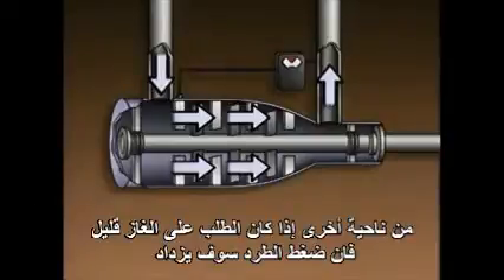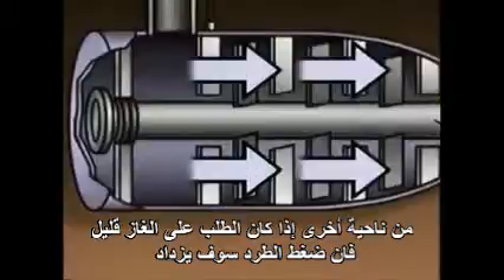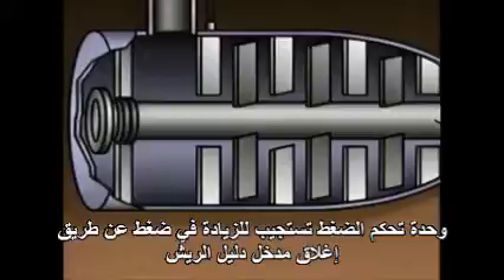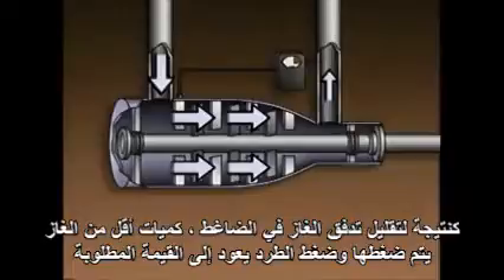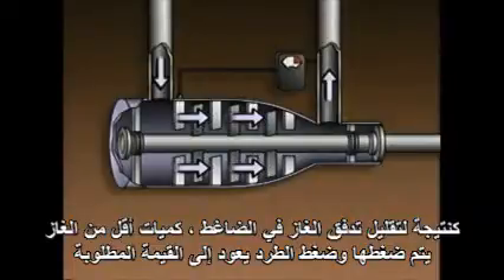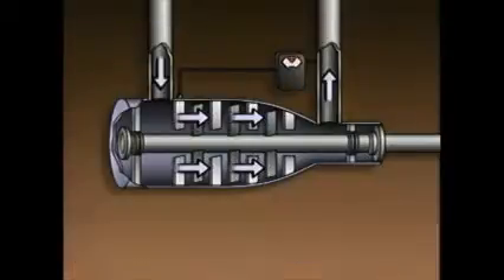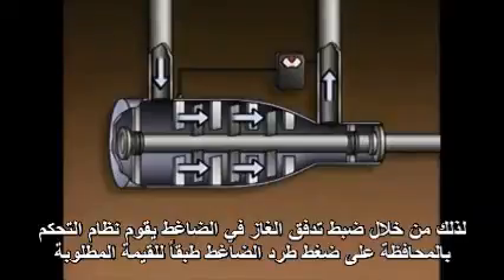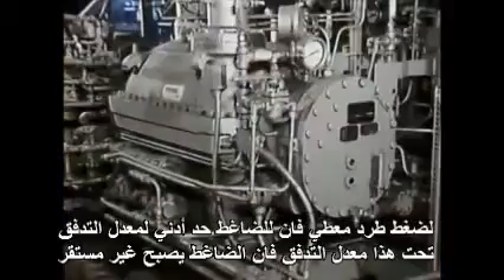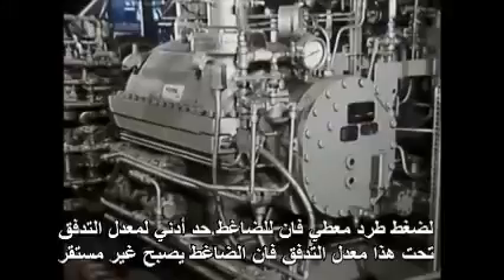On the other hand, if the demand for gas decreases, discharge pressure increases. The pressure controller responds to the increase in pressure by closing the inlet guide vanes. As a result, the flow of gas into the compressor is reduced. Less gas is compressed, and the discharge pressure returns to the desired value. So, by adjusting the flow of gas into the compressor, the control system maintains the discharge pressure of the compressor at the desired value. For a given discharge pressure, a compressor has a certain minimum flow rate.